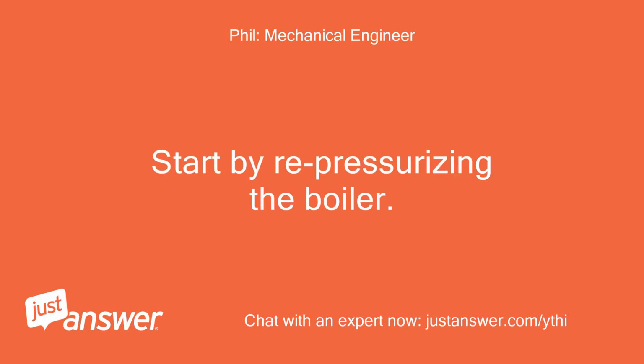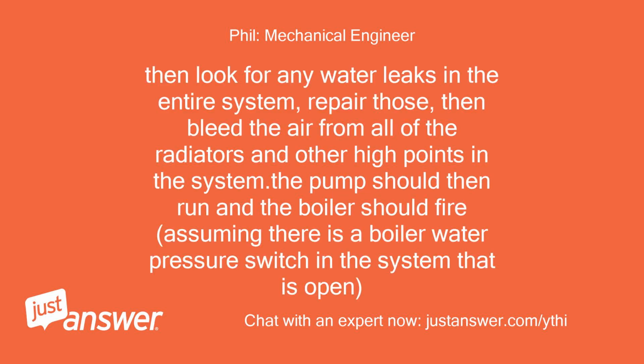Start by re-pressurizing the boiler. Then look for any water leaks in the entire system, repair those, then bleed the air from all of the radiators and other high points in the system. The pump should then run and then the boiler should fire, assuming there is a boiler water pressure switch in the system that is open.